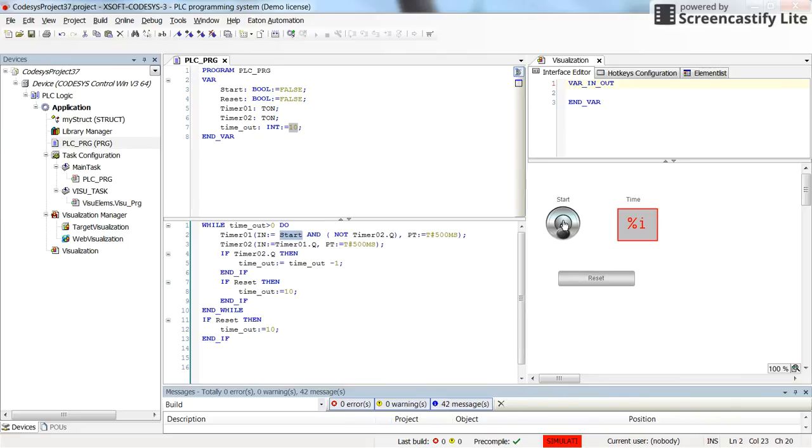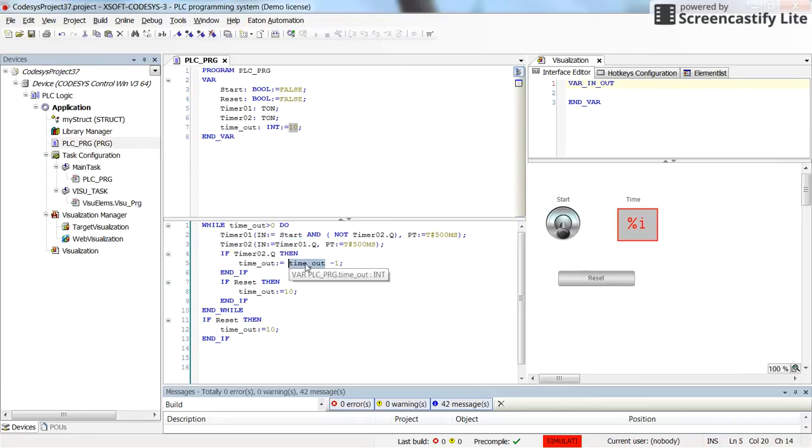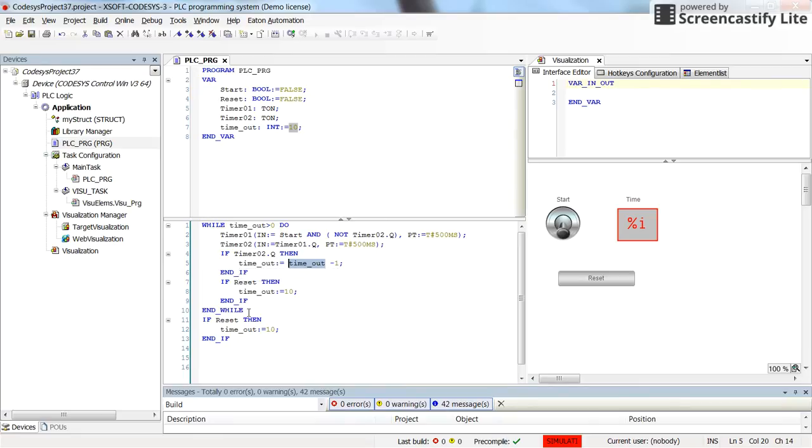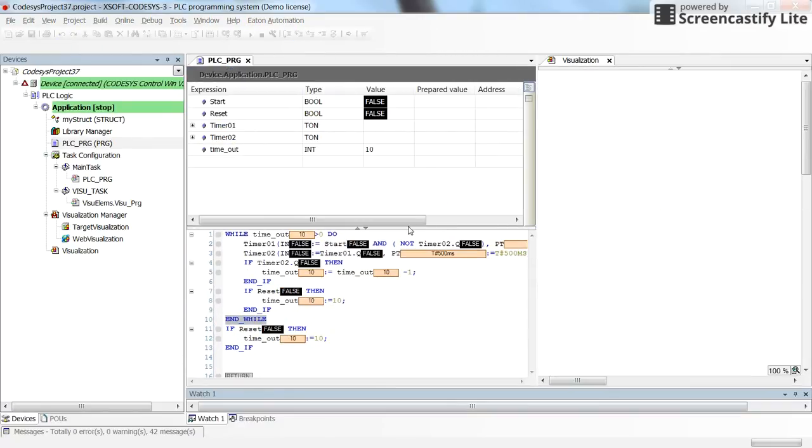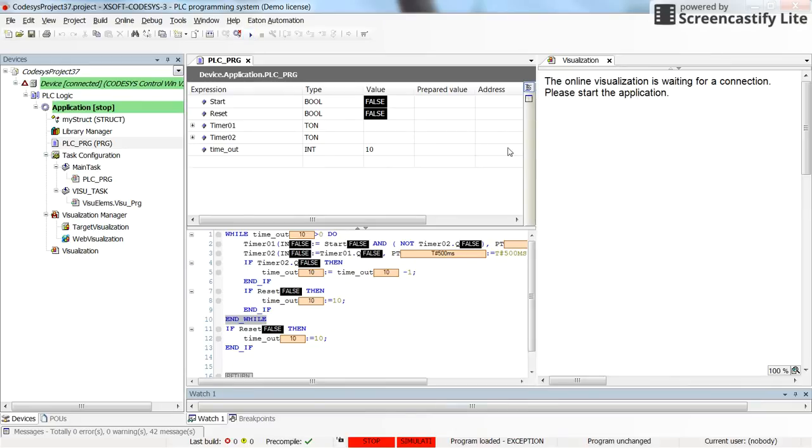So in the first timer the input is start and then not of timer 2.q. So if the value coming from start is true, then the timers will work. If not, timers will stop and accordingly the value of the timeout will not be reduced, it will not be decremented. So this is the way that you can use the while instruction in the structure text. Let me just log in and run it so you can see the execution of the program in the runtime.